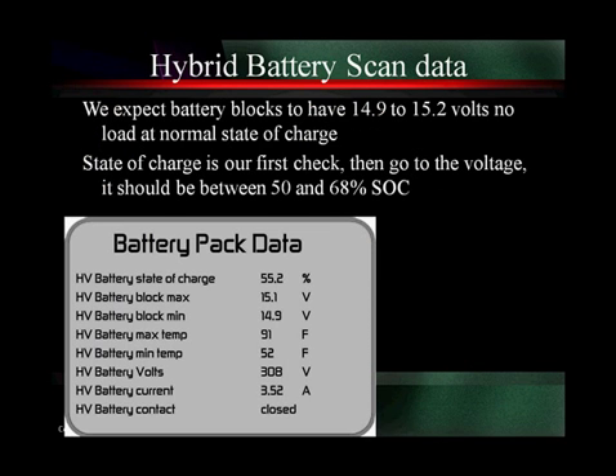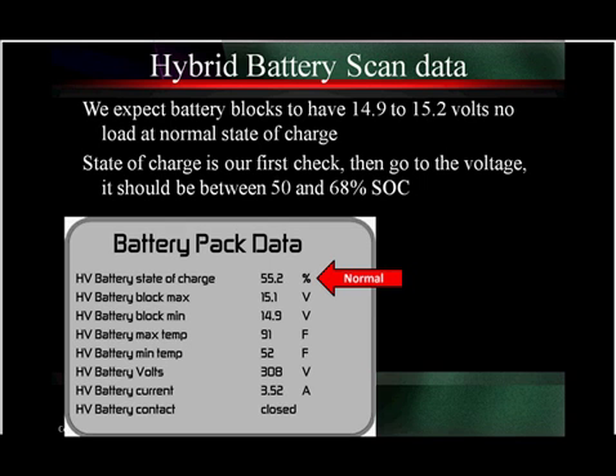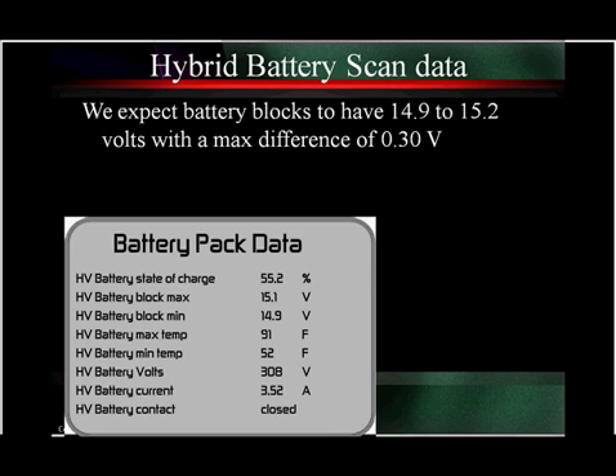Our 14.9 to 15.2 has a couple cautions: we have to have no load and be at a normal state of charge. So we start off by looking at state of charge first, then we go look at the voltage. State of charge has to be between 50 and 68. Looking here, we have 55.2. That's perfectly normal, as long as you don't have excessive current draw, which we'll look at later. We can now judge our batteries.